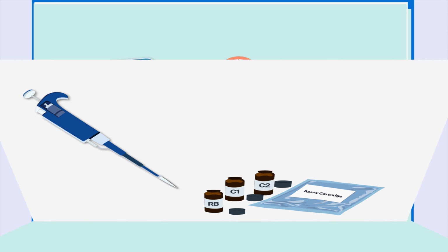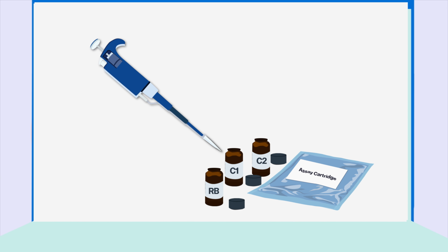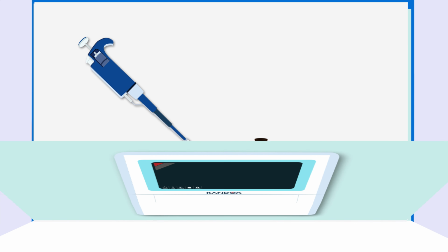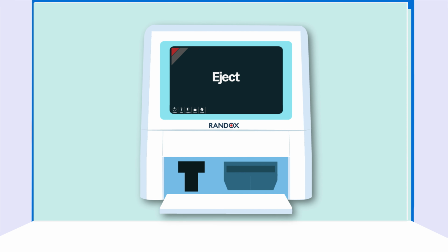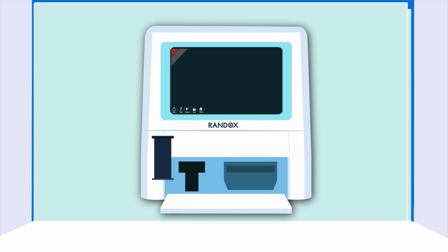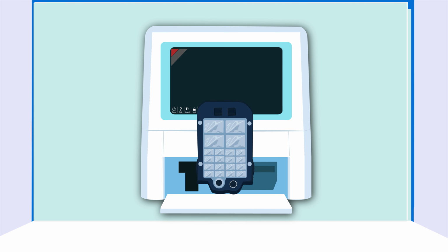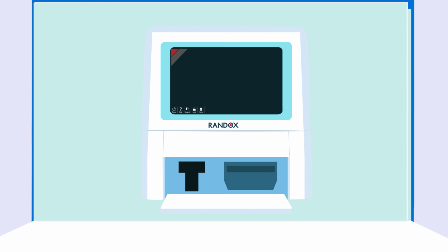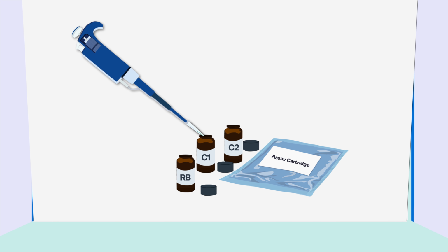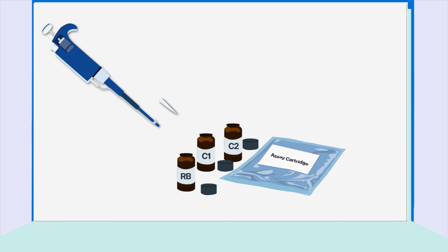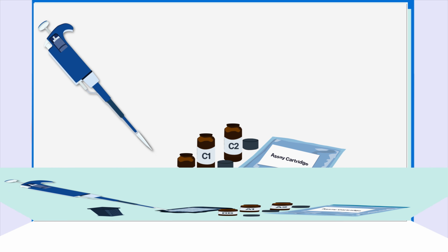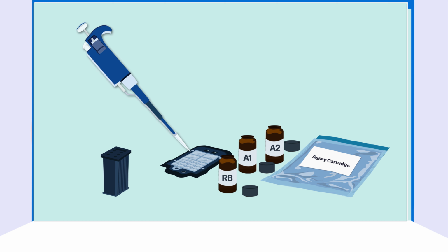At this point, the quality control vials can be reconstituted. Once the second run is complete, select Eject Drawers and remove the used cartridges to discard into biohazardous waste. The device will then generate a prompt to perform Control Run. This is the final run of the device calibration, the quality control check. Now, using the quality control vials that you reconstituted, repeat the same process that you carried out in the first and second run.